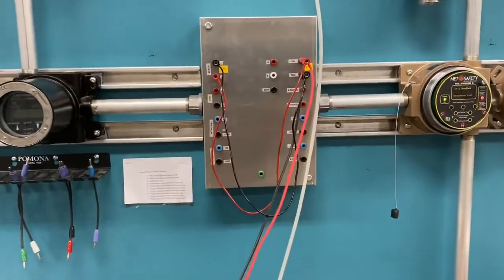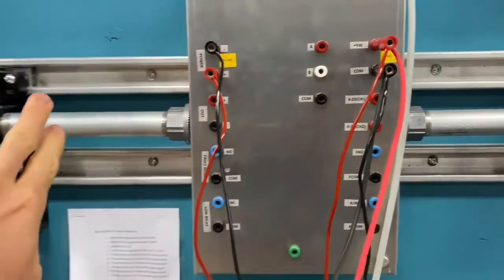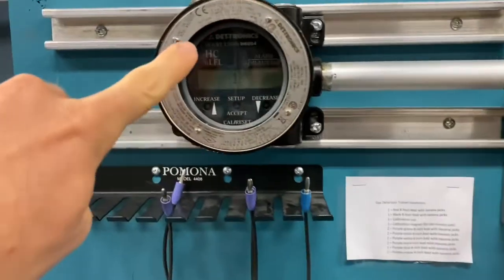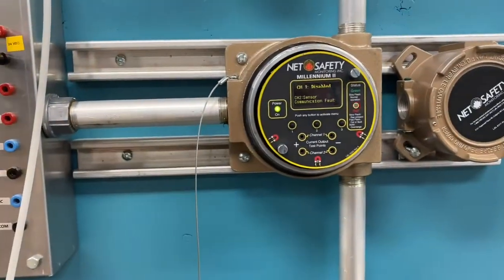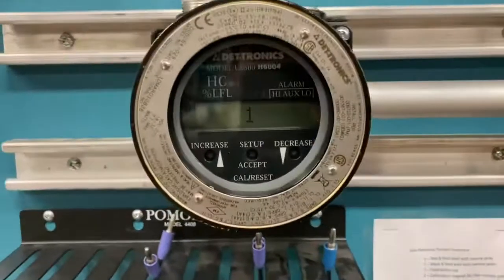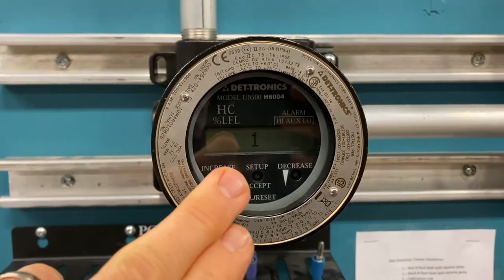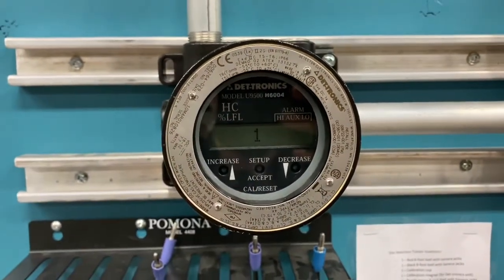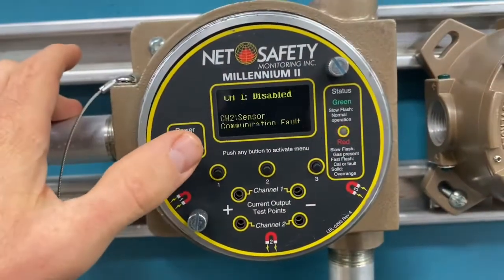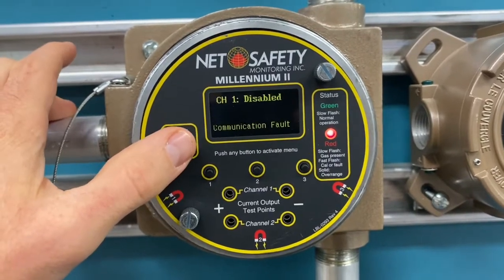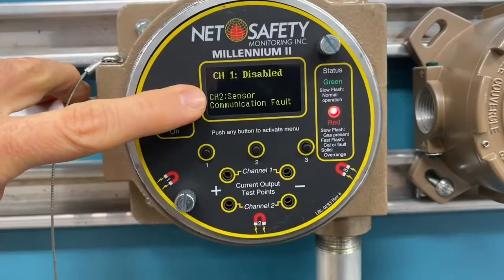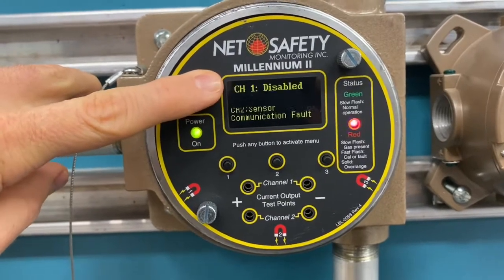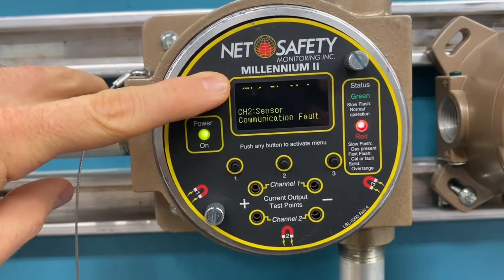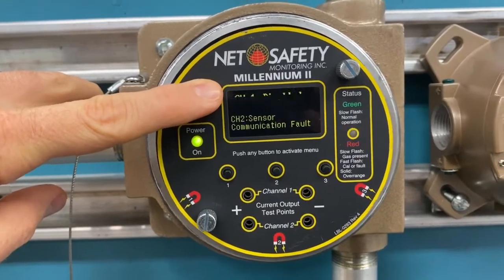All right, so you can see I've got power run over to both units. I've got power run over to the Infinity, the Det-Tronics system here, and the Millennium 2, or the net safety right here, is powered up. The only thing you can see over here, we're reading about 1 right now, 1%, and you can see how it's in percent LFL instead of LEL, which is the same thing. And then over here, we've got a communication fault, and it's because the toxic gas sensor's on channel 2. Channel 1 has the LEL sensor, the explosive gas sensor.